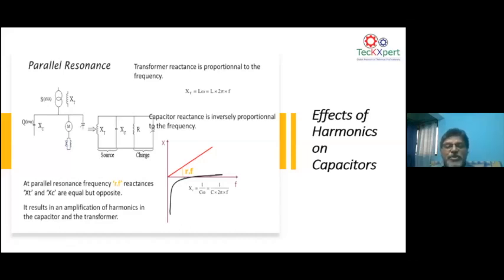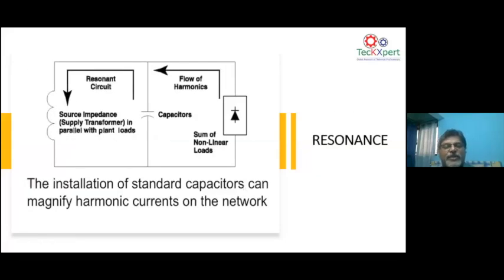So what you generally have is a frequency relationship between the inductance and the capacitance. At the point where the inductive impedance and capacitive impedance become equal and opposite, you have a resonant frequency. Now, looking at the resonant frequency in a little more mathematical form, consider the network with capacitors along with the rest of the network. When I say source impedance, it means your generator source impedance, the transmission from the generator to your transformer, the transformer impedance, then the cable impedance from the transformer to your load. All that becomes your source impedance.